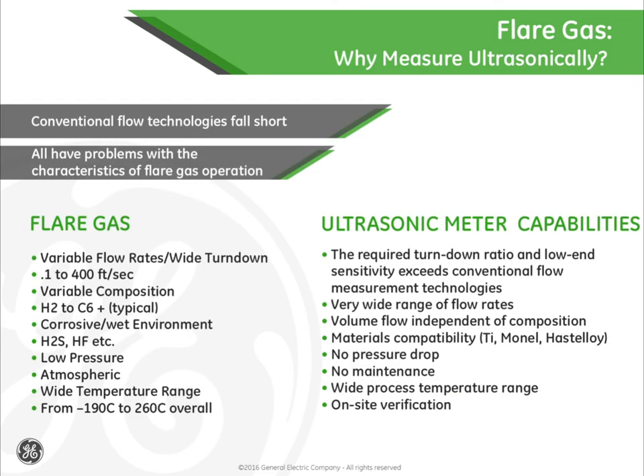All conventional flow technologies fall far short when measuring flare flow gases. All flow technologies except ultrasonic have problems with one or more of the requirements for proper flare gas flow measurement. Flare gases have highly variable flow rates and wide-ranging gas compositions. The measurement environment is often corrosive, wet, and dirty, and measurements are taken at or below atmospheric pressure over a wide range of temperatures. In this backdrop, a flare meter needs to operate at an unprecedented level of reliability since most flare gas is considered a pollutant and is subject to regulatory observation. Ultrasonic meters are the only technology able to endure the demanding measurement requirements in a flare.